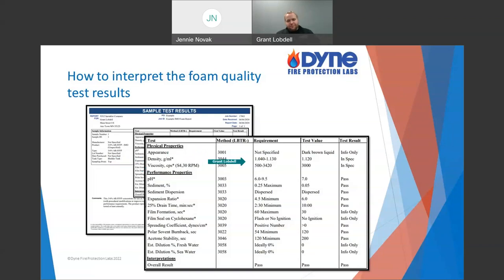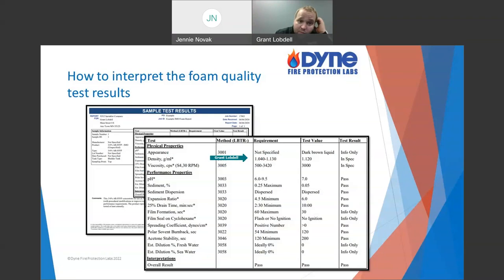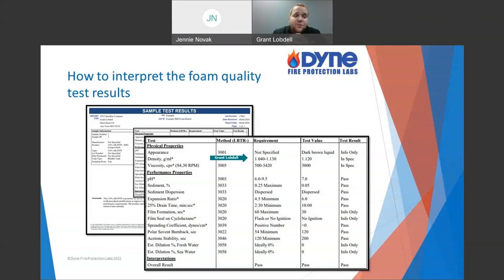Looking at the physical properties: density and viscosity. For density — this product is supposed to have a specific range, and the value of 1.12 shown falls within that range, so it meets spec. But what if it doesn't? If density is low — say less than 1.04 — that probably means there's been some dilution, some water getting in. Water's density is around 1.0 (seawater is about 1.02). So if density is low, the first inclination is that it's been diluted with water or contaminated with something else, like a different foam.